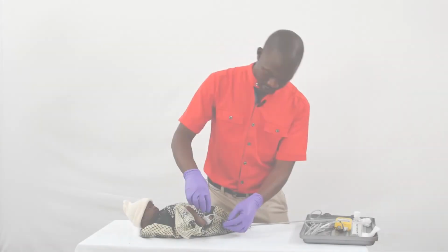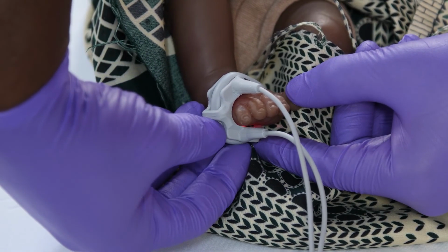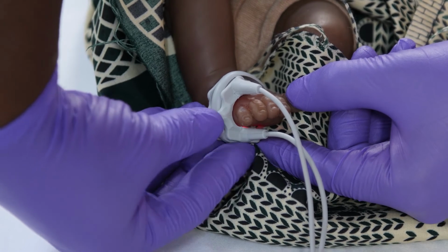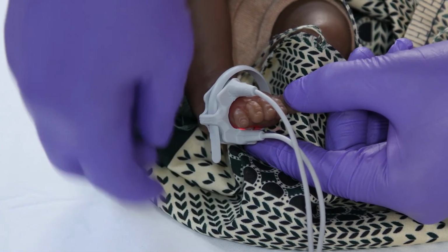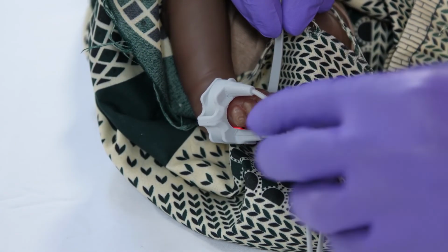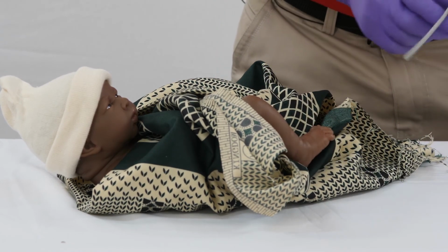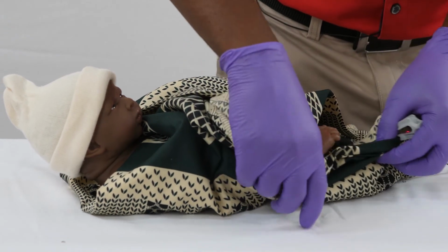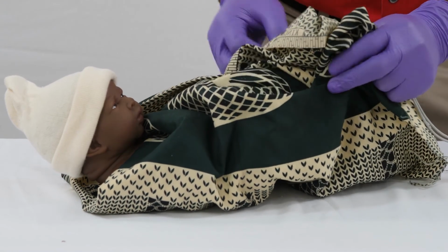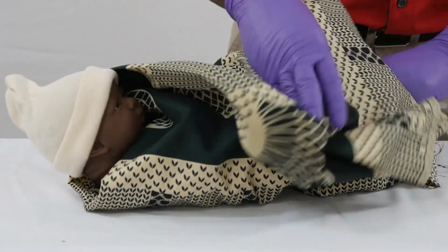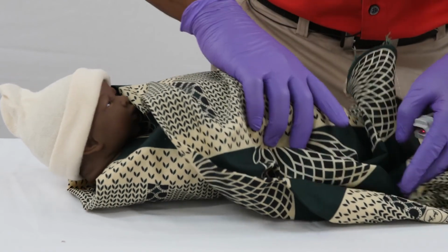It is also important to know that if you have a very sick baby with extremely low saturation levels, below 70%, then the pulse oximeter readings cease to be accurate. If you are continuously monitoring, you need to move the probe around and not leave it on the same site for prolonged periods. It can cause pressure sores or other damage to the skin. Once you have your reading, you can take the probe off. Make sure you wrap the baby back up so that it doesn't get cold.